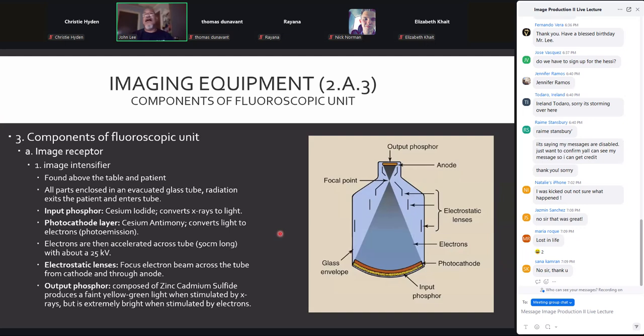With our image intensifier, again, this is a diode. So with a diode, we have current that flows from cathode to anode. The image intensifier tube has a cathode, but the x-rays exit the patient and once they go through the glass, they strike the input phosphor, typically made of cesium iodide. Cesium iodide is prominent in radiography because it reacts so well to x-rays at producing light. Okay, so first thing we do, the input phosphor converts x-rays to light.